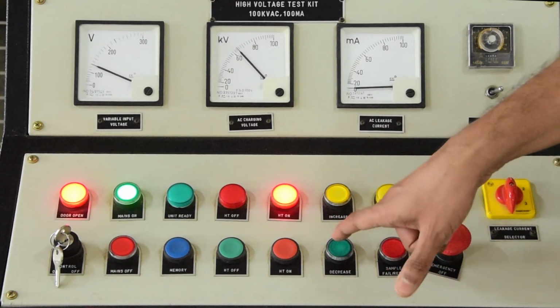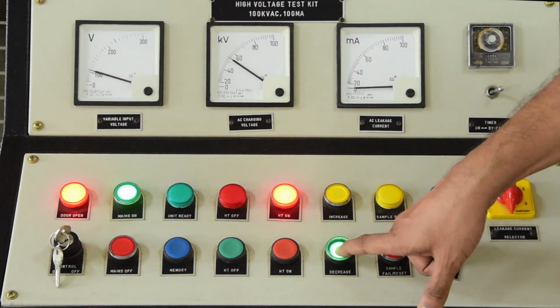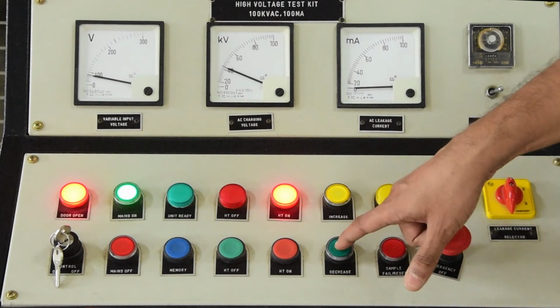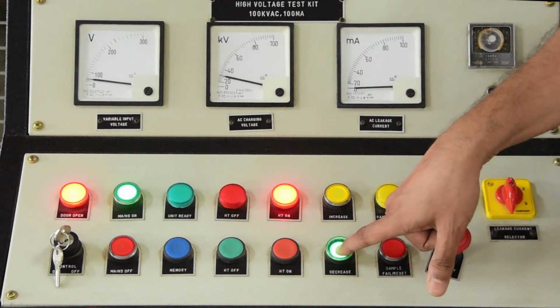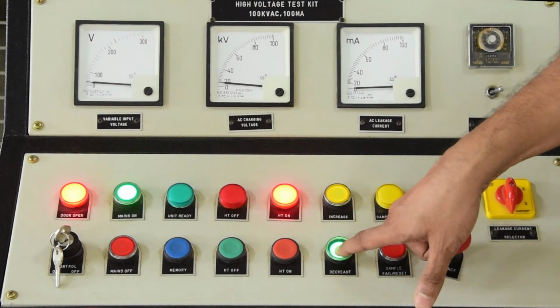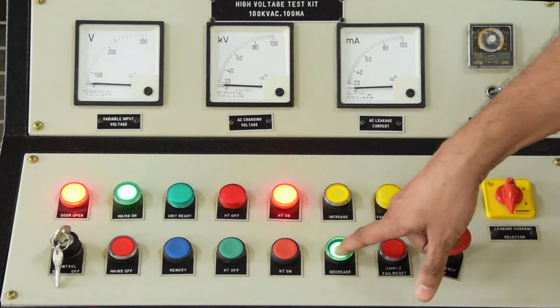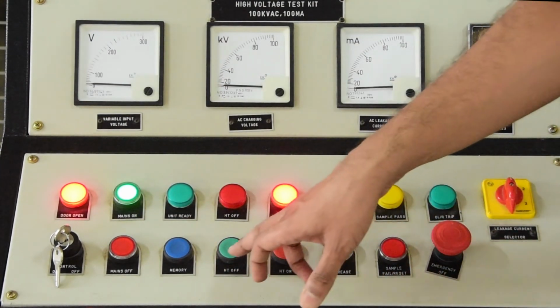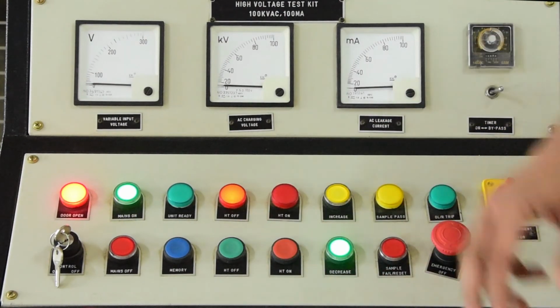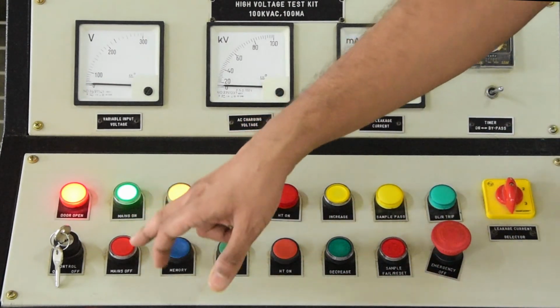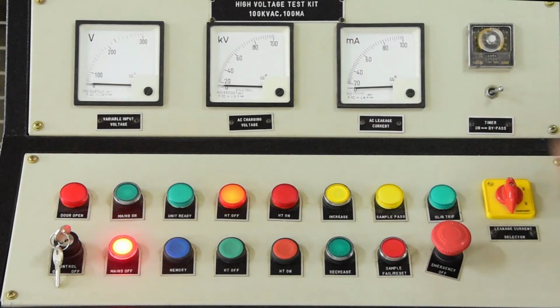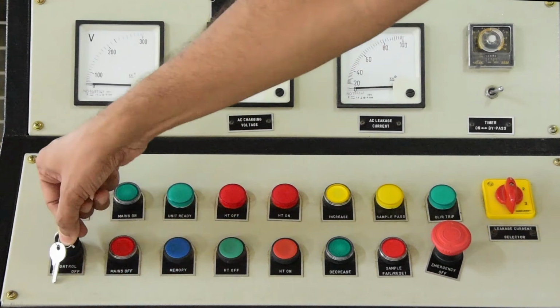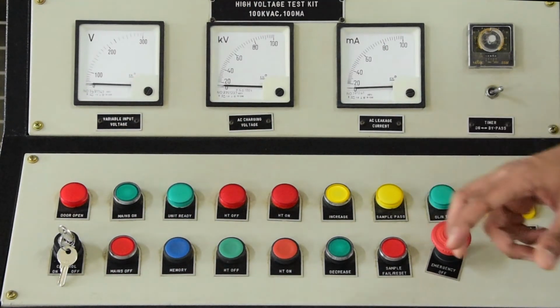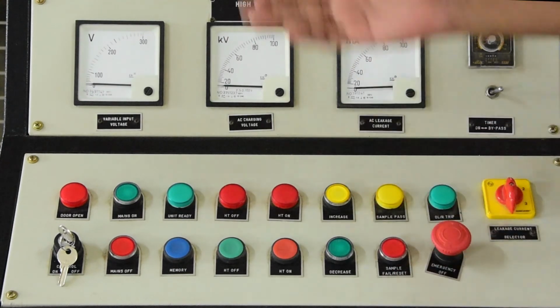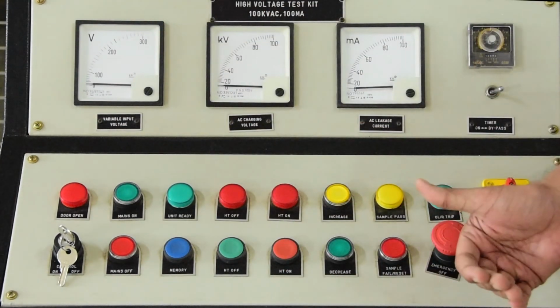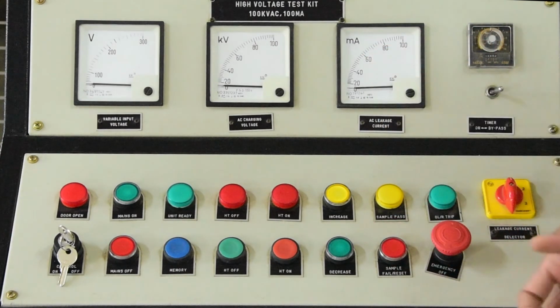Now, before moving ahead and adjusting the spacing between the electrodes, after noting down the observation, we have to decrease this voltage gradually by pressing the lower, or decrease, switch. You can see that the potential is going down to 0, and once it is reduced to 0, we switch off the supply by pressing HT off, and then press the mains off switch. So the supply is disconnected, and we turn off the key and go for adjusting the spacing between the two electrodes to a new value, repeating this procedure in order to obtain the spark over voltage.